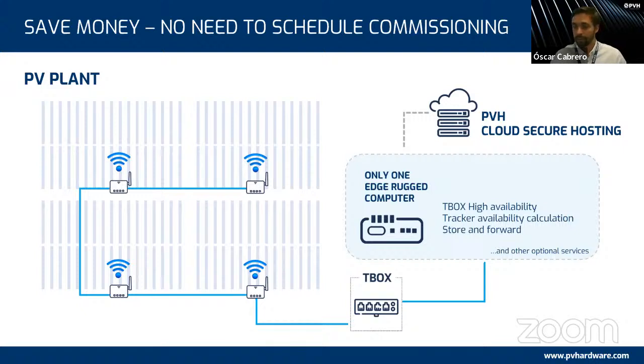ProInsights offers a very easy and simple solution to monitor, by cloud, the whole PV plant, using only one rugged computer for the entire plant. That means only one device needs to be installed in the O&M building or substation building, and with a direct connection to the T-box, it will retrieve all the data. It will be very easily commissioned and will send that data to our secure cloud hosting.